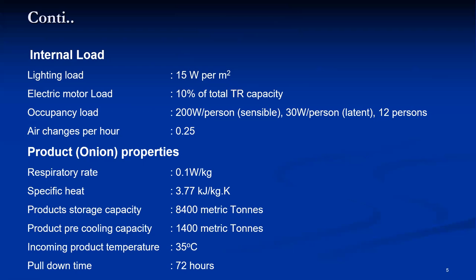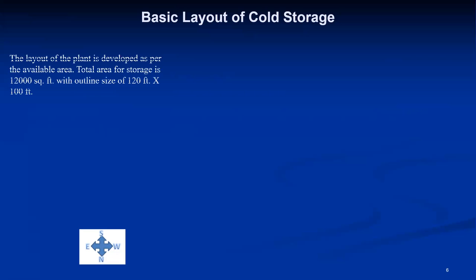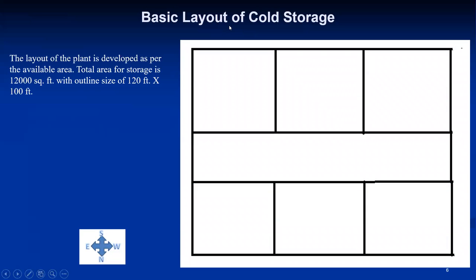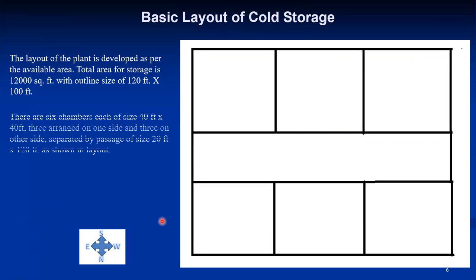Based on the design data, the layout of the cold storage can be developed. As per the available area of 12,000 square feet, a rectangle of 120 feet by 100 feet is used. This entire area is divided into 6 chambers. The 120-foot side is divided into 3 sections of 40 feet each, and the 100-foot side is divided into 40, 20, and 40 feet, with the 20-foot section serving as a passage for loading and unloading.